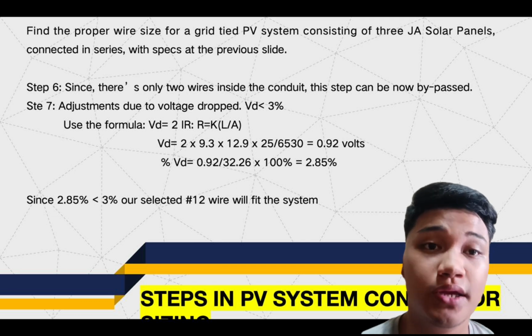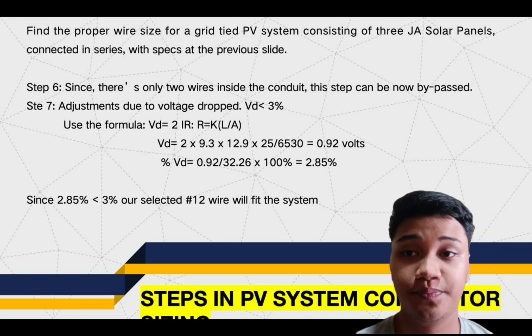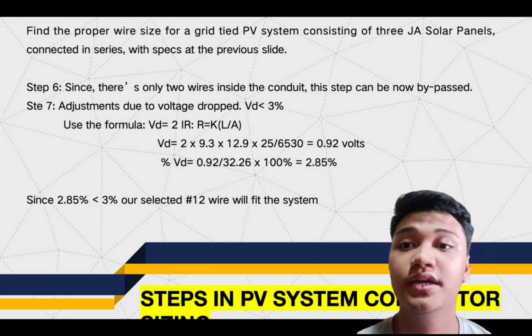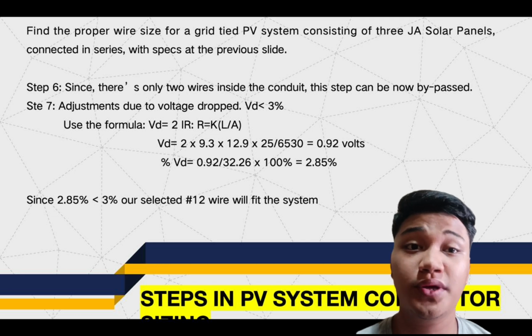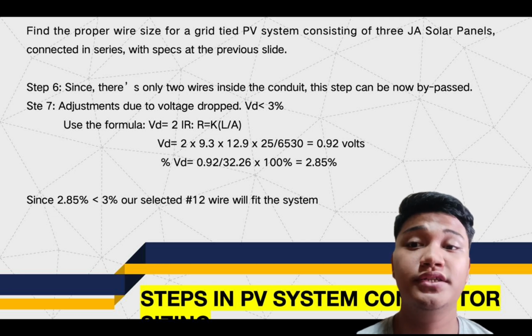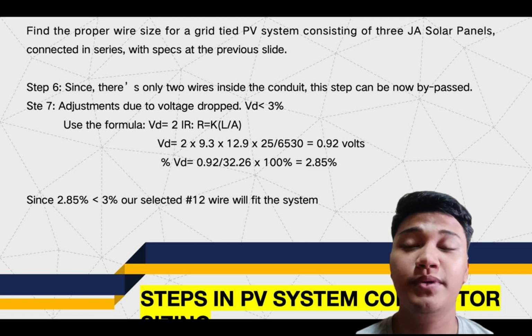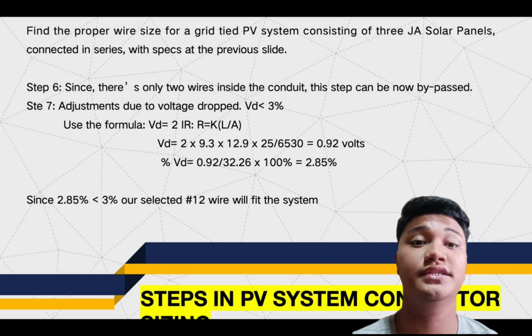Yung 9.3 po na yun, makikita natin sa JA Solar panels. Yan, yung voltage drop natin, 0.92 over 32.26 times 100% is equals to 2.85%. Ngayon, since 2.85% is less than 3%, our selected number 12 wire will fit the system.